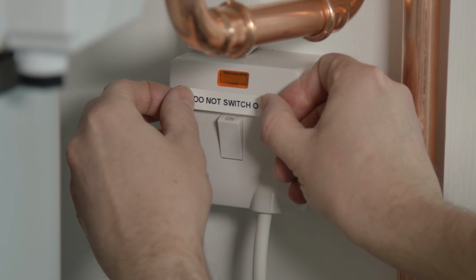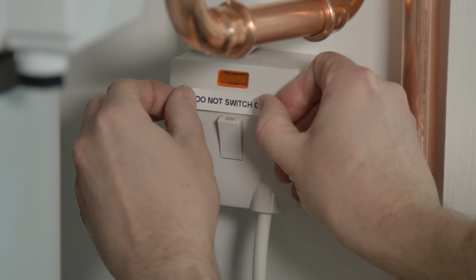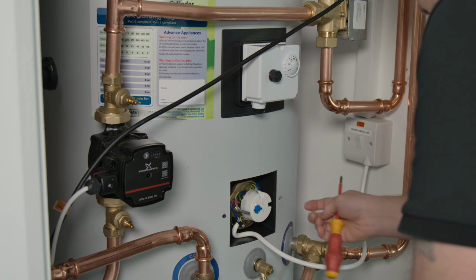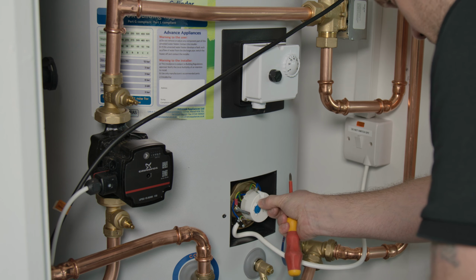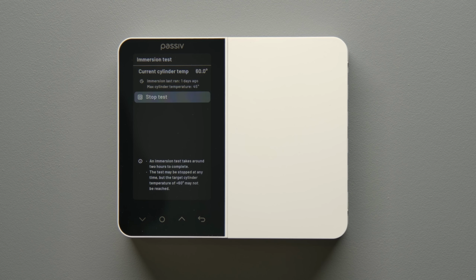Also ensure that the local isolator is labeled to avoid the user powering it off, and that the high temperature thermostat is set to maximum. After the test has exceeded 60 degrees Celsius, the test can be stopped.